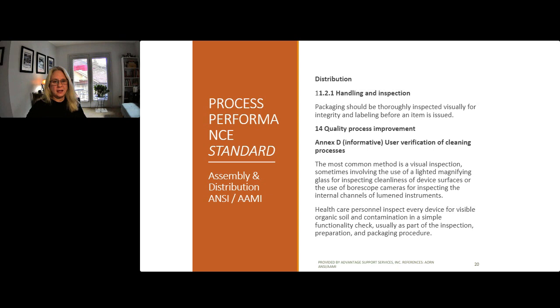Another guideline is visual inspection combined with other verification methods that allow the assessment of the inner housing of channels, testing cleaning efficacy of equipment, monitoring key cleaning parameters. So in your department, you can assess, right now within your own facility, what is your cleaning verification process? And is it in all points of inspection? Are you just checking them when they come off the washer, a surface area? Are you also inspecting internal channels?